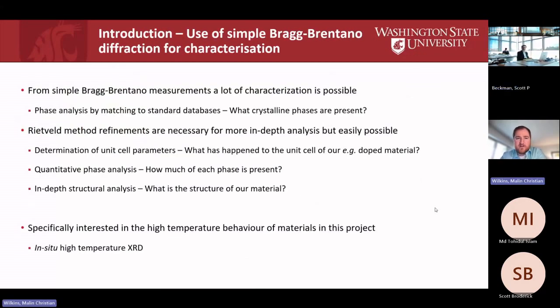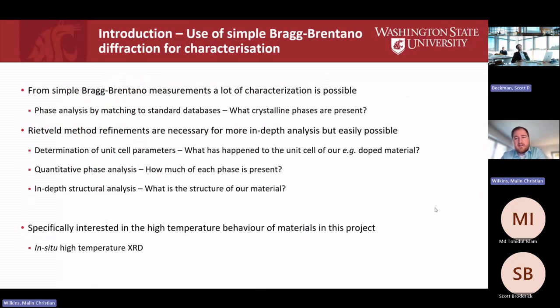From simple Bragg-Brentano measurements, which is just a way of setting up the diffractometer, we can get quite a lot of information on what's in the sample. The most common is phase analysis — what crystalline phases are actually present — generally done by matching to standard databases. There's a whole field called Rietveld refinement, which is necessary for more in-depth analysis, and is definitely possible from lab data.